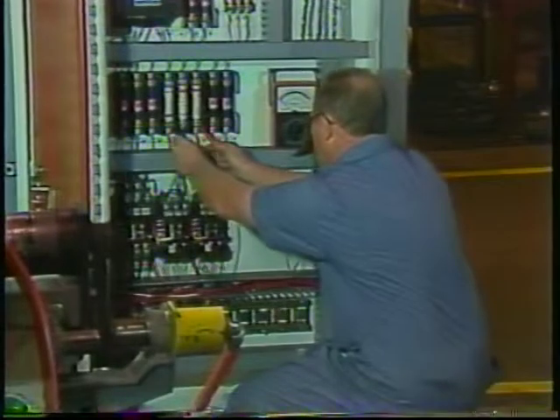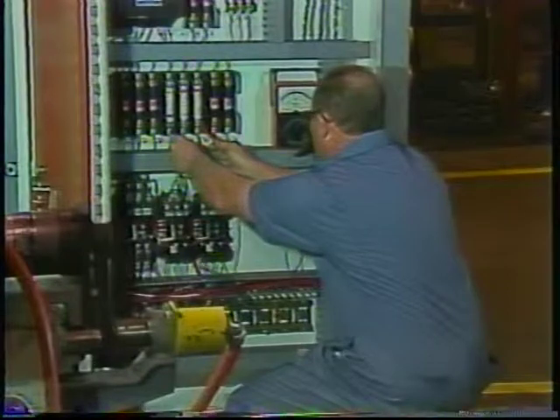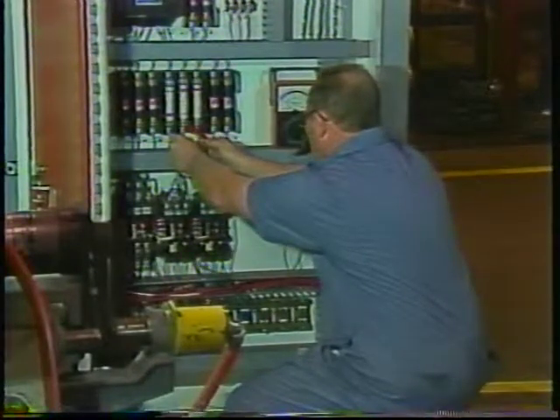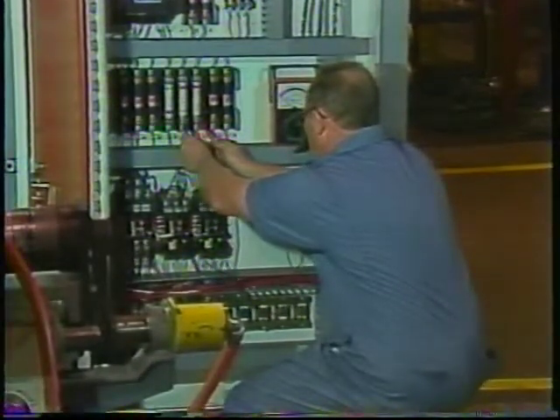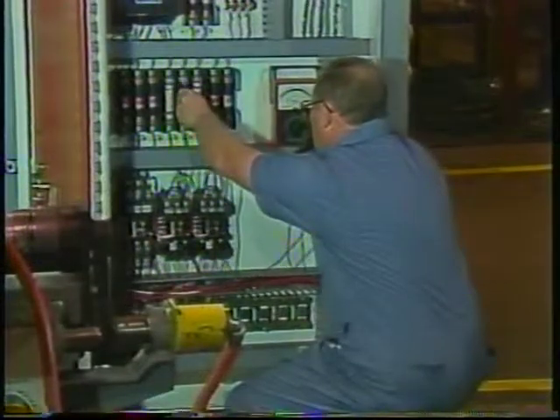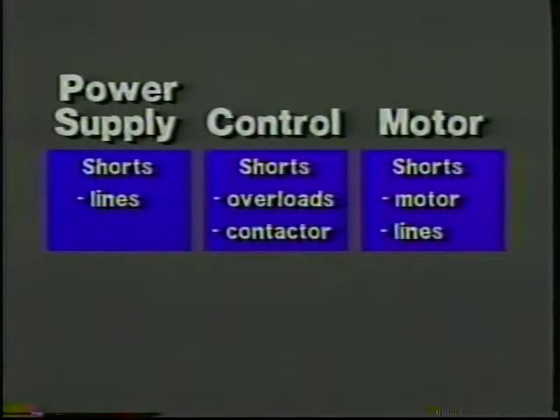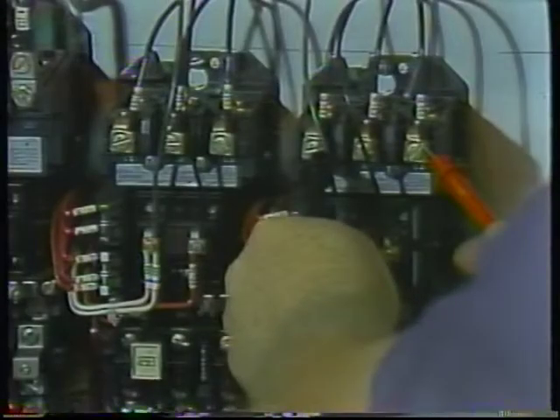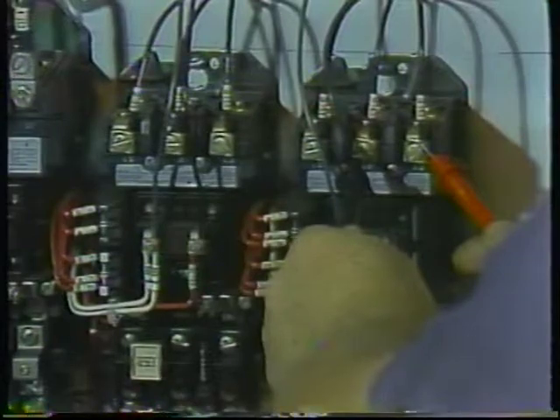Go to the main panel or breaker box and check. If you find a blown fuse or tripped breaker, it could be because of a one-time condition of some kind, like a lightning strike on the line. But more likely, there is a short somewhere in the system. It is dangerous to just reset the breaker or replace the fuse and turn the power back on. If there is a dead short in the system, breakers can explode. So first, check voltage to make sure the breaker is really tripped.